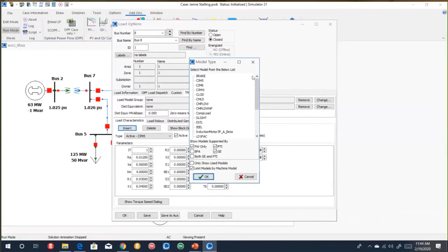It's actually a PSSE model, but there are similar ones. I've set it up on a 100 MVA base, and I took all the default parameters with the exponent set to 1, so it's not a constant torque, it's a linear torque.